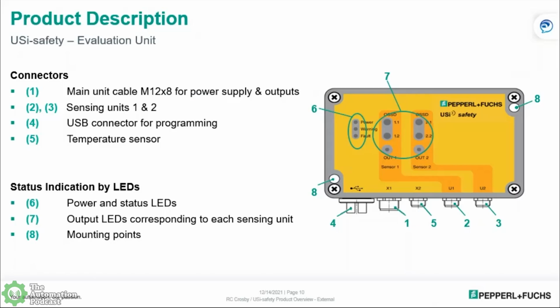And I think another thing, just to reiterate, is you do not actually have to have two sensors. That's only if you had two areas that you needed to sense. But that's not required for the operation. If you only had a single area, you only need a single sensor, it'd still be safety rated, correct? Correct. Absolutely. So each channel carries its own safety rating.